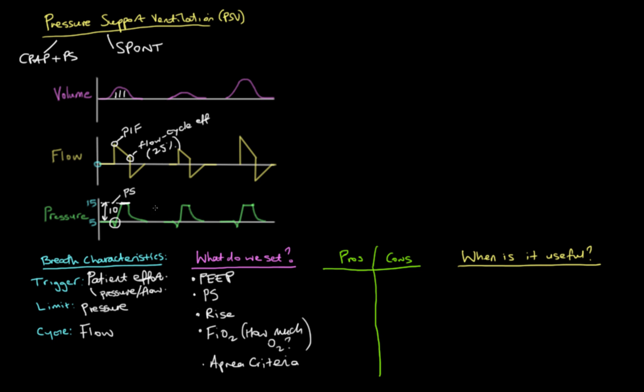What is rise? Rise is essentially how quickly we rise up to the peak pressure that we've set. We're going from 5 up to 15 — that change in pressure is 10. How quickly we go from 5 to 15 is the rise. In one example you can see it goes almost straight up from 5 to 15 immediately. In another it's on an angle — that's a slower rise. Rise time is how long it takes to get from 5 up to 15.